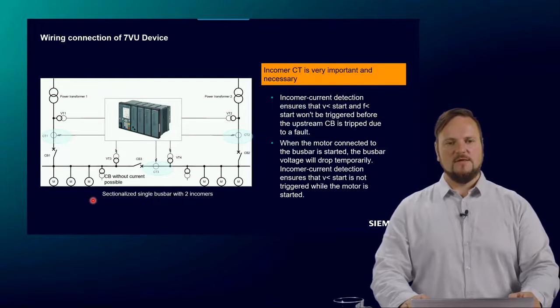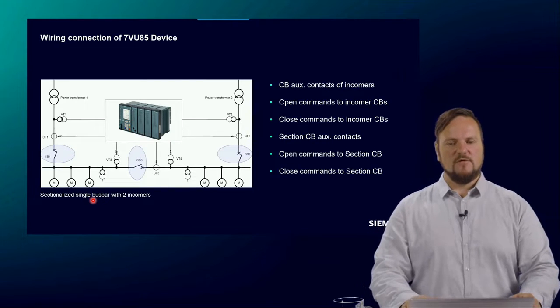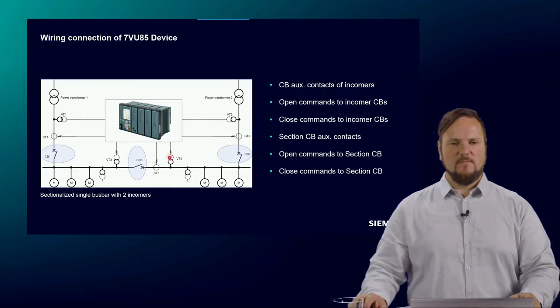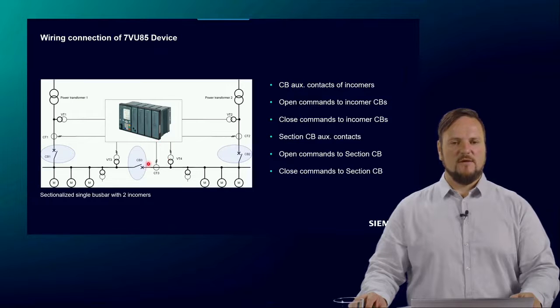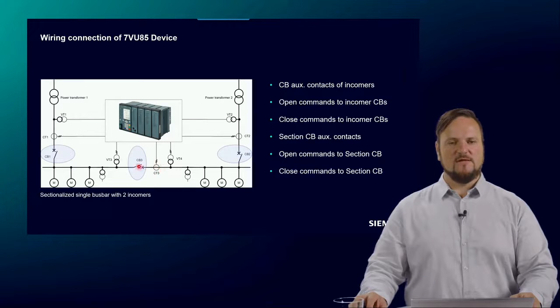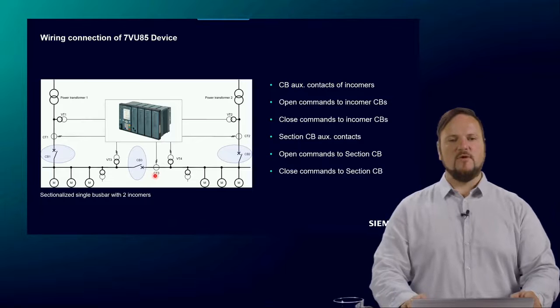We also need the circuit breaker position — auxiliary contacts of the incomer, open commands, and close commands of the incomer, and on the section CB as well. One important note: the current transformer on the section CB is not necessary. With version 9.30 and 9.40, the CB without current function was implemented. It is therefore not necessary to add current to that CB — you can use the new function group CB without current and save some money on additional current inputs.